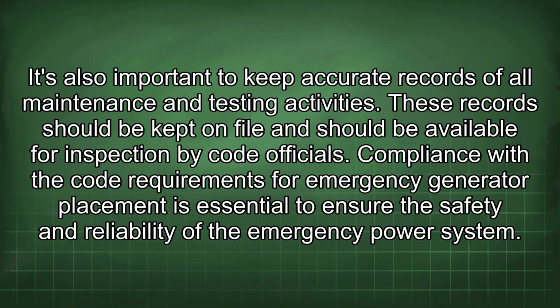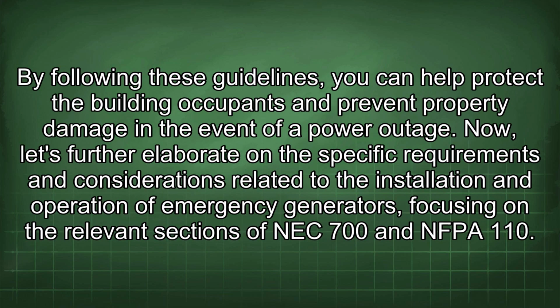Compliance with the code requirements for emergency generator placement is essential to ensure the safety and reliability of the emergency power system. By following these guidelines, you can help protect the building occupants and prevent property damage in the event of a power outage. Now, let's further elaborate on the specific requirements and considerations related to the installation and operation of emergency generators, focusing on the relevant sections of NEC 700 and NFPA 110.